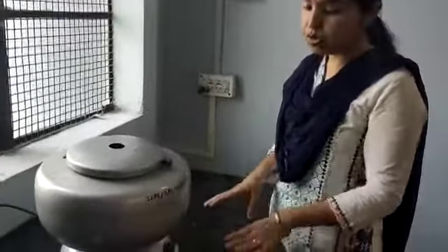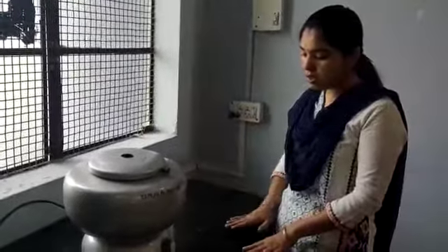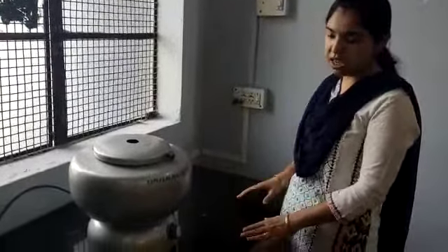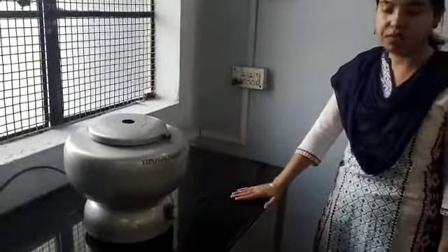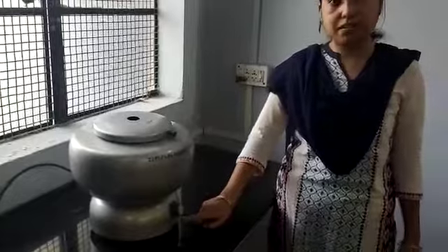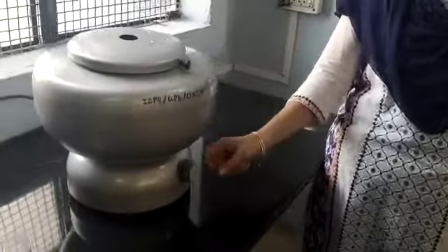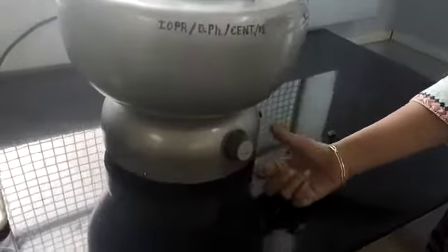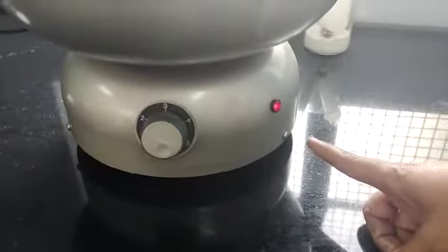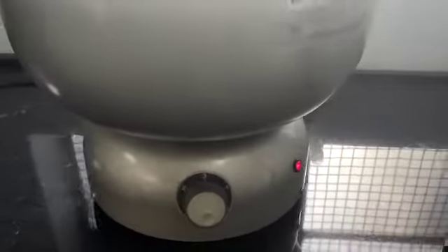Before we start the centrifuge, we need to remember some important instructions. Make sure that the centrifuge is placed on a platform which is steady and free from vibrations. As you can see, this is a steady platform and it is free from vibrations. Also, the knob should be at 0 so that when you switch on, the empty samples do not run automatically, which may damage the equipment. So it should always be at 0. Before starting, insert the 3-pin plug of the centrifuge into the 3-pin socket. Then switch on. You can see that the pilot lamp is turned on. The red light indicates that the pilot lamp is on, which indicates that power is being supplied to the centrifuge.